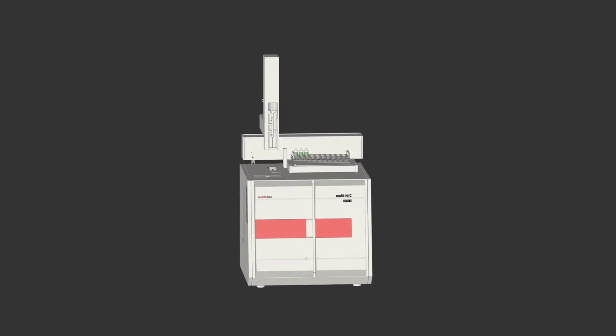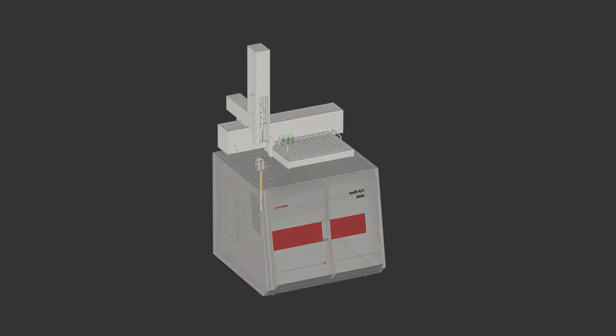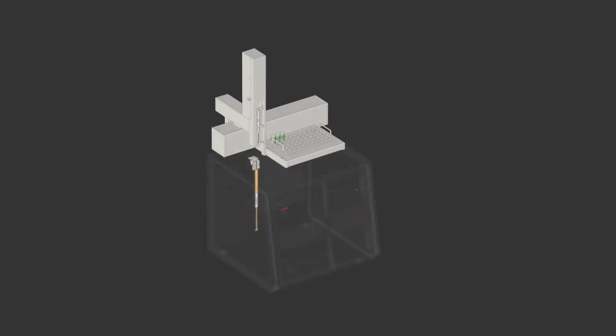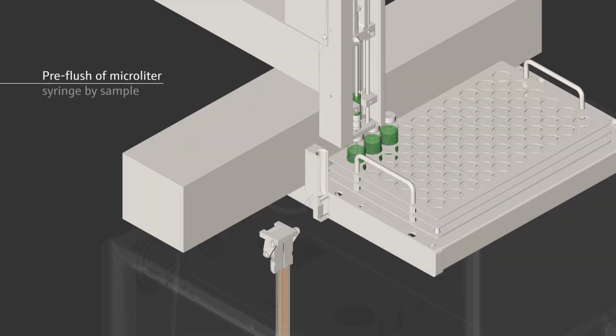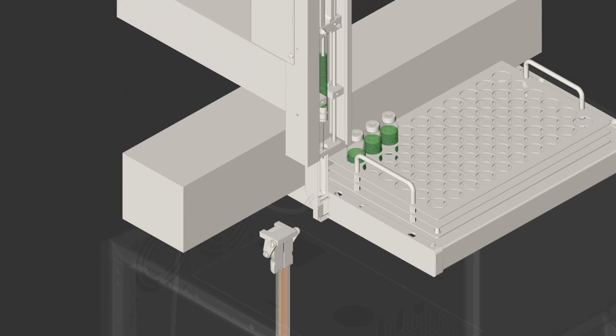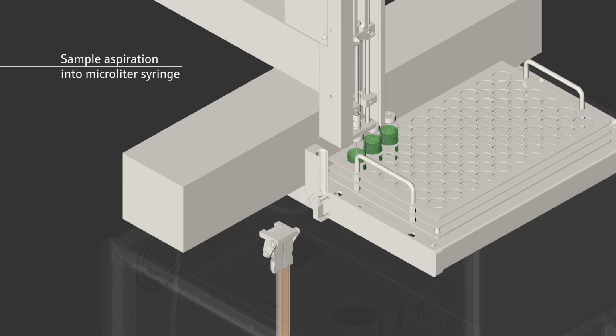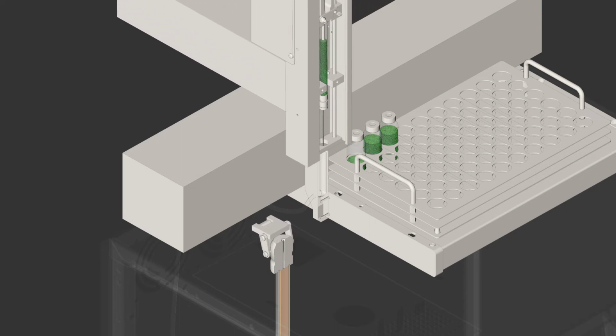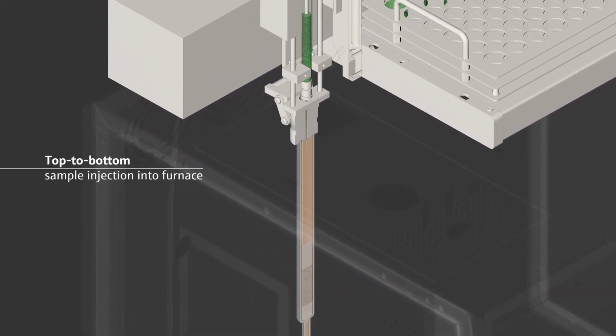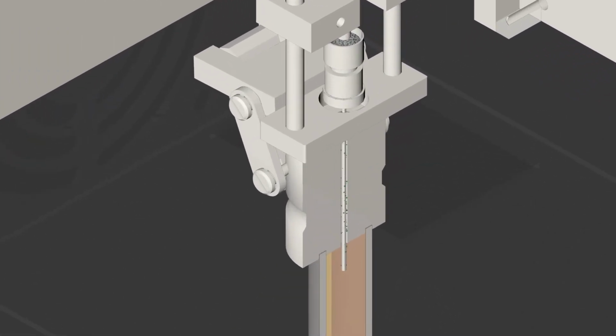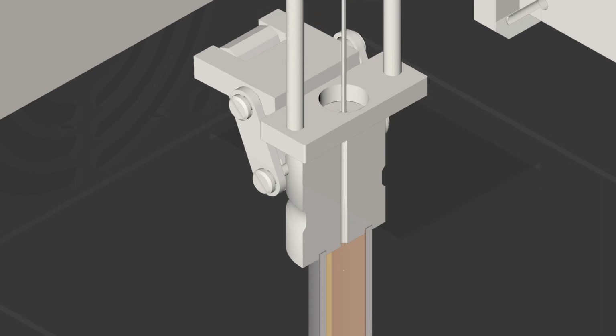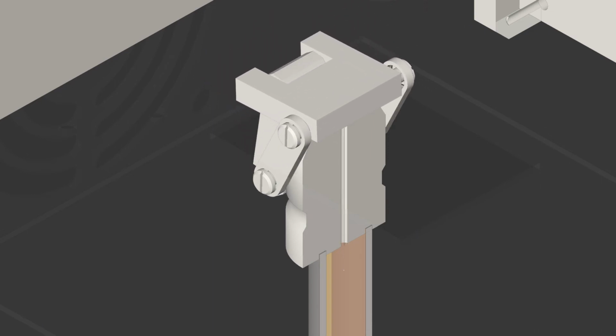When dealing with heavy particle-loaded or oily samples, Analytik Jena's direct injection technique is the solution of choice. The sample is directly taken up into the microliter syringe, with a rinsing step included. The septum-free direct injection is done top to bottom by a wide-bore needle with complete particle transfer. No tubes and valves are needed. The injection needle is thermally cleaned in the furnace head during measurement. The syringe is pre-flushed with the next sample, thus carryover is reliably minimized.